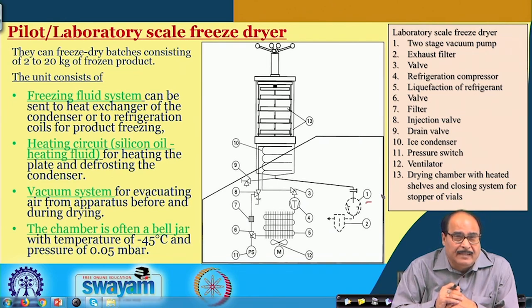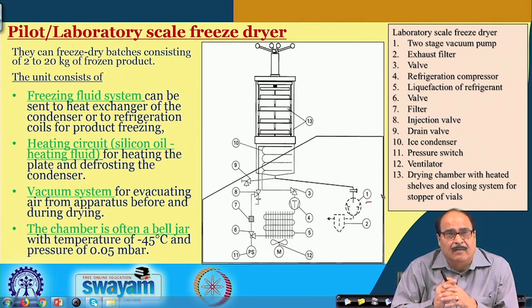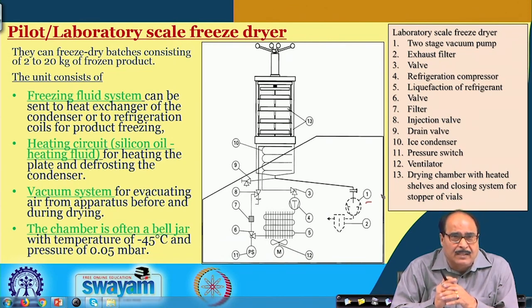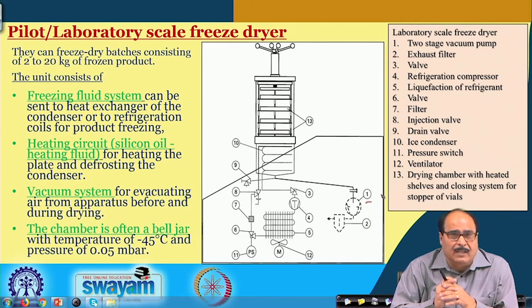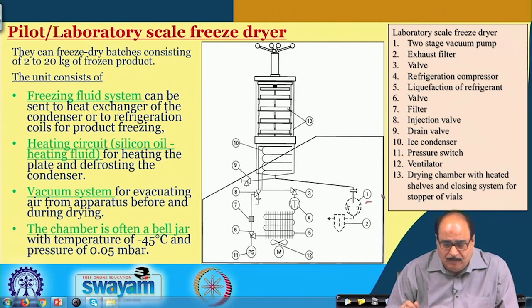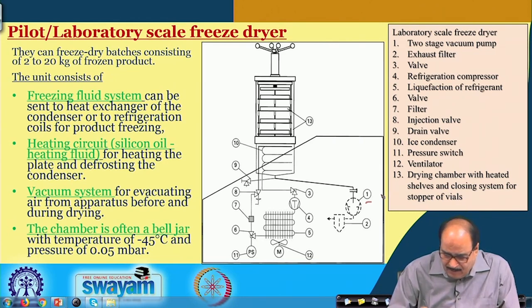The heating circuit normally uses silicon oil heating fluid for heating the plate and defrosting the condenser. It consists of a vacuum system for evacuating air from the apparatus before and during the drying process. The chamber is often a bell jar with a temperature of around minus 45 degrees Celsius and a pressure of about 0.05 mbar.